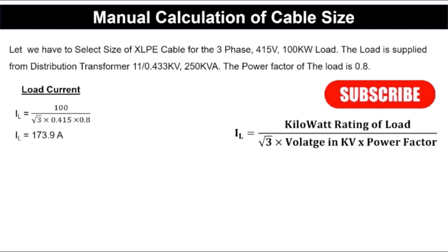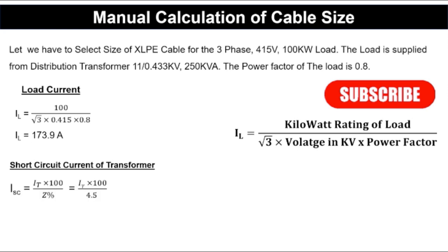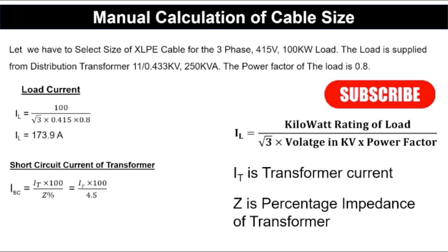The formula for short circuit current rating is: ISC = IT × 100 / Z%, where Z% is the percentage impedance of the transformer. Here we have taken Z% = 4.5. The percentage impedance of a transformer generally varies from around 4%. You can get these values from the manufacturer or from the ETAP library, but here we have taken 4.5.